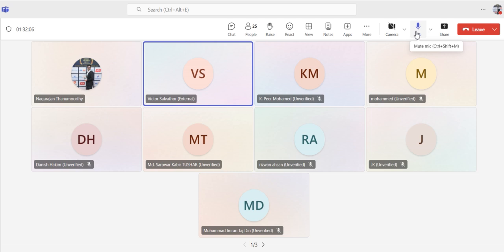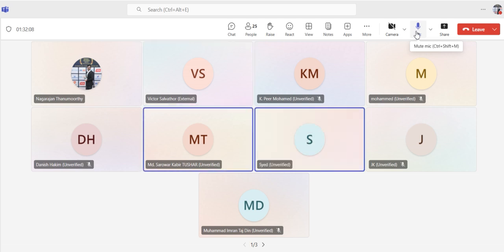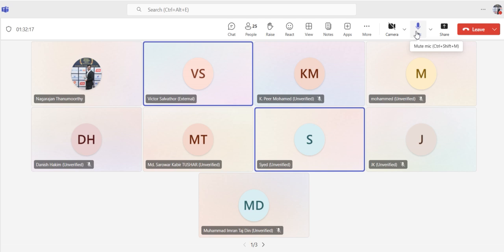You have a return pipe as well, right? Yes. So we need to look at the difference in the vertical height of both supply and return. That difference has to be considered, not the entire line. Exactly. Because there is a parallel supply as well as return, we have both. Only the difference between the vertical height of supply and return is to be considered. Exactly, that's the one you have to consider.